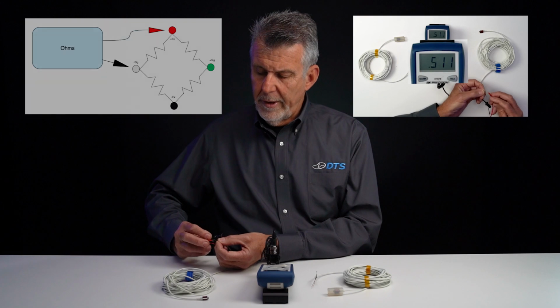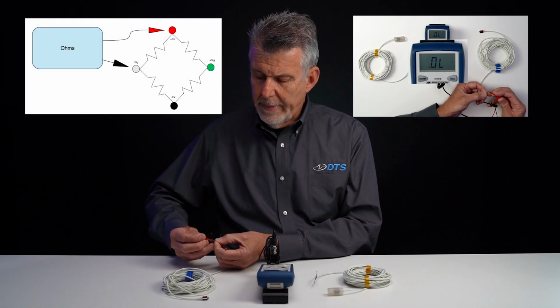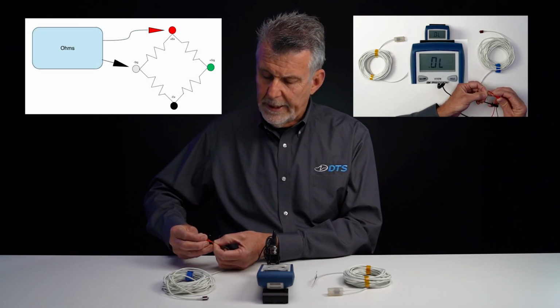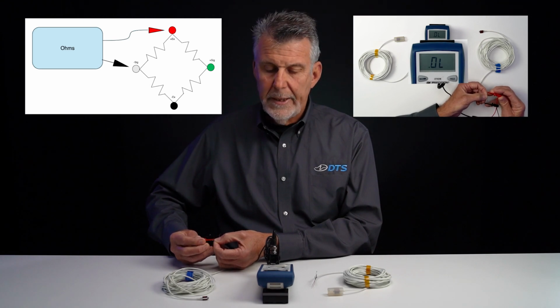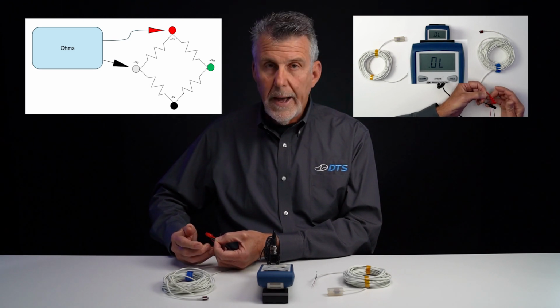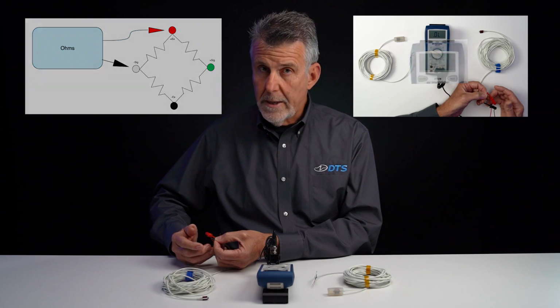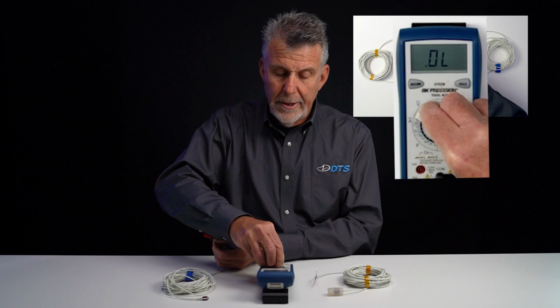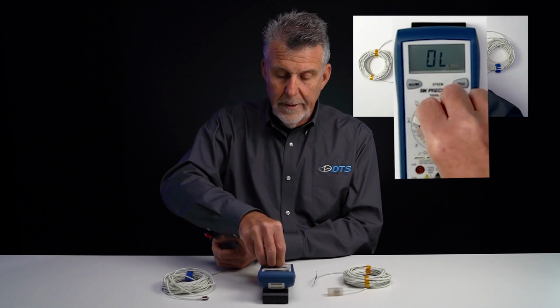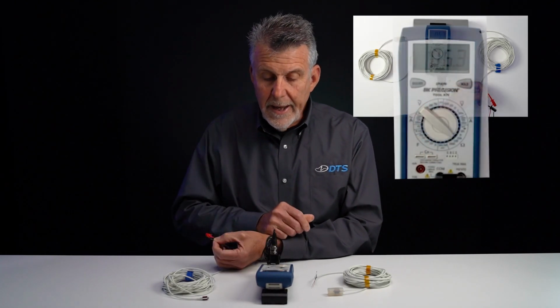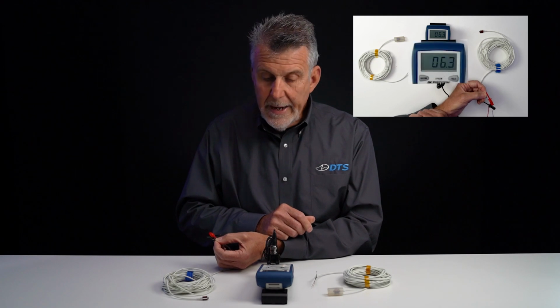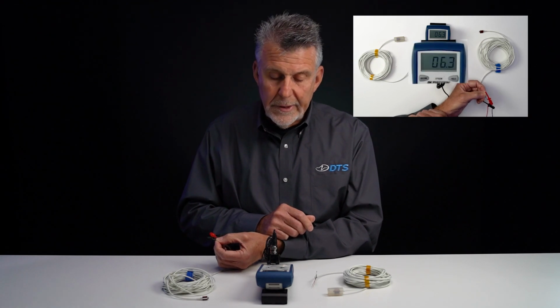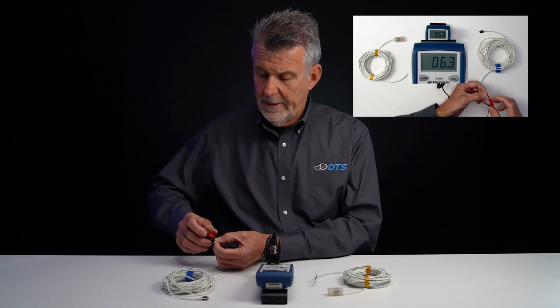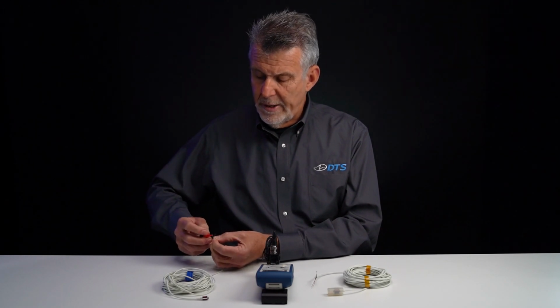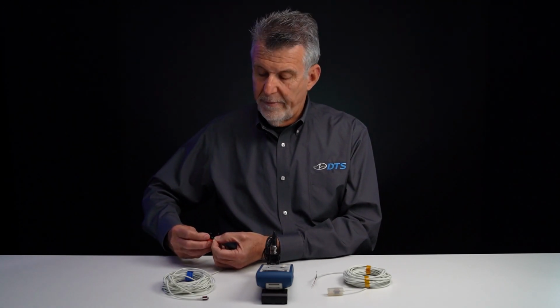Now I'm going to move over and check the minus signal side by going between the plus excitation and the minus signal. And I get an open circuit. And I'm going to turn the range up on the multimeter to 20,000 ohms full scale to see if I can get a reading at all. And I get a very high reading of 6.3 kiloohms. Okay, that immediately sounds much different than what I saw before.